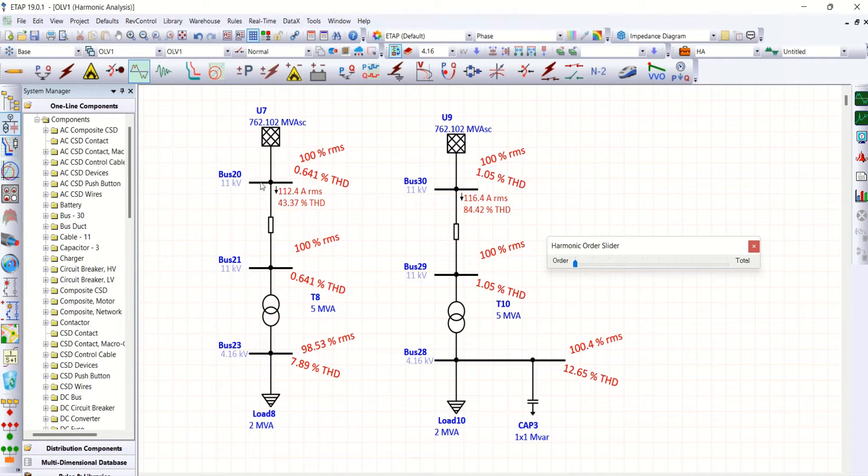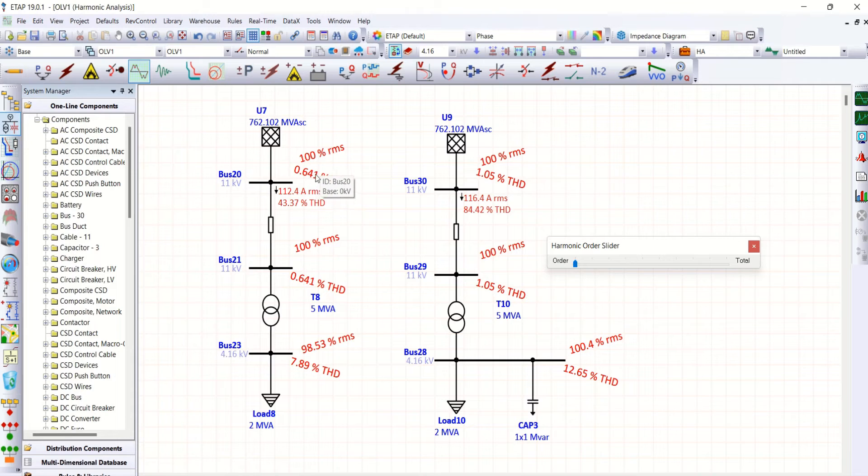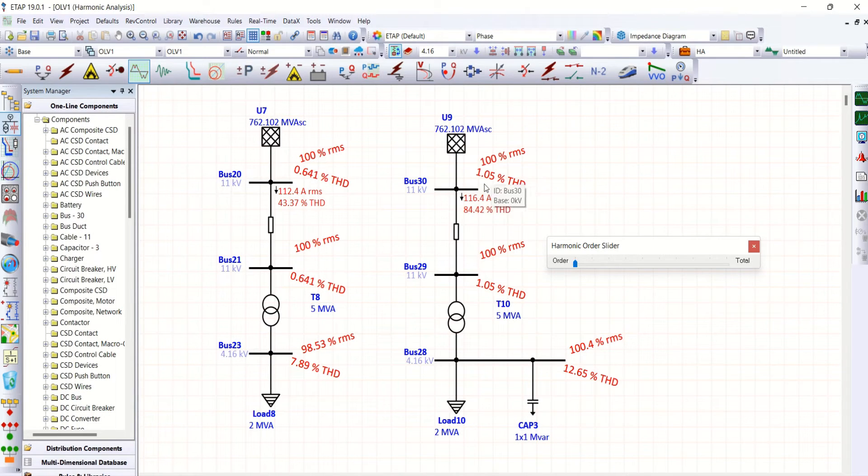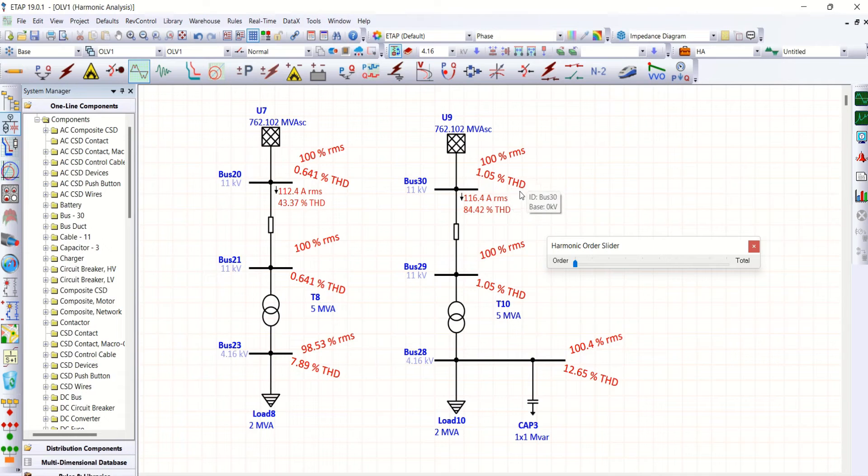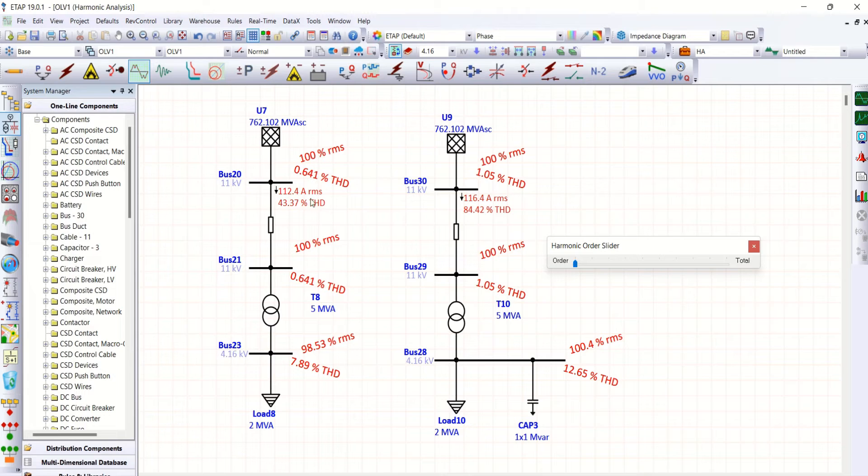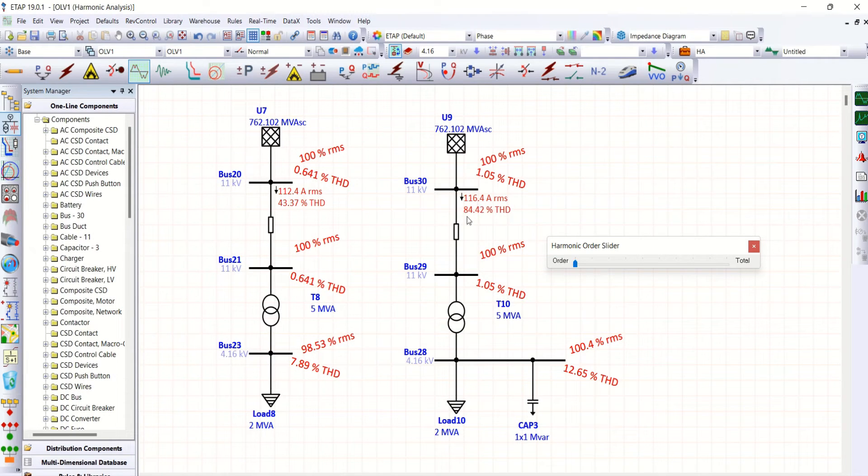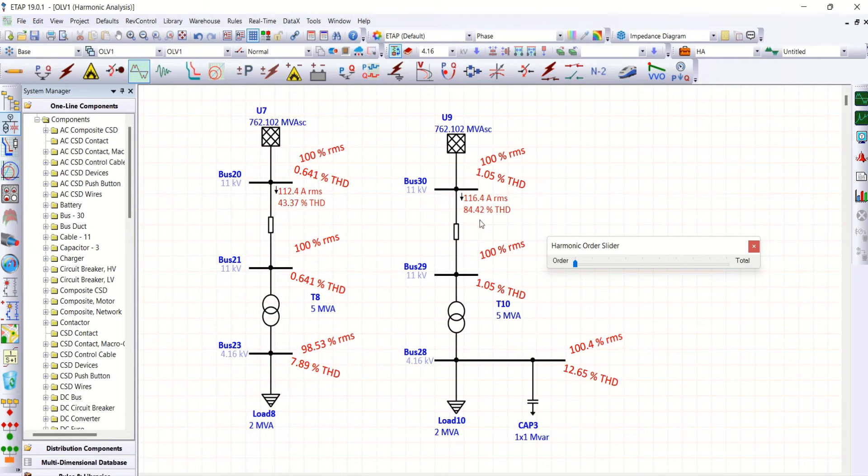Now coming to grid side. Have a look at Bus20, 0.641% THD, whereas the system with capacitor bank has 1.05% of THD. Now coming to current distortion, 43.37% of THD for the system without capacitor bank. The system with capacitor bank, it is likely doubled, almost doubled here, 84.42%.